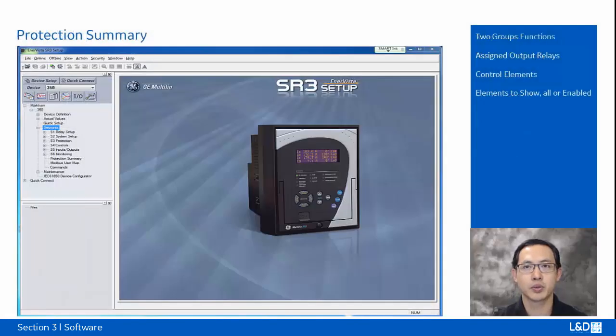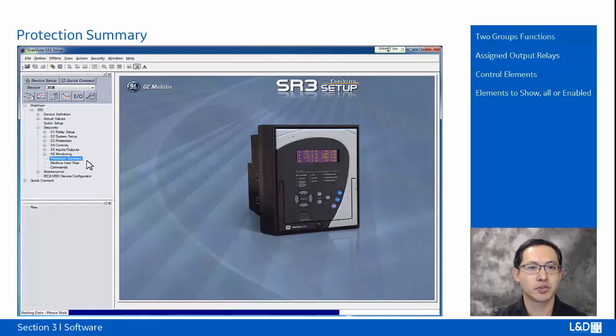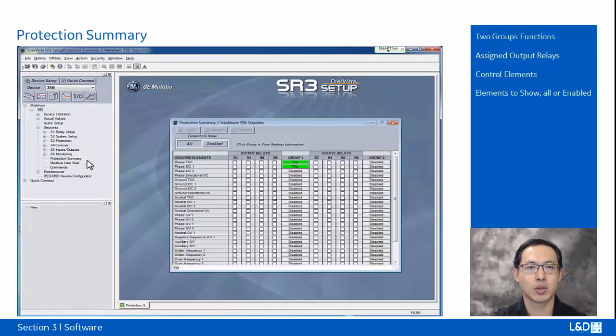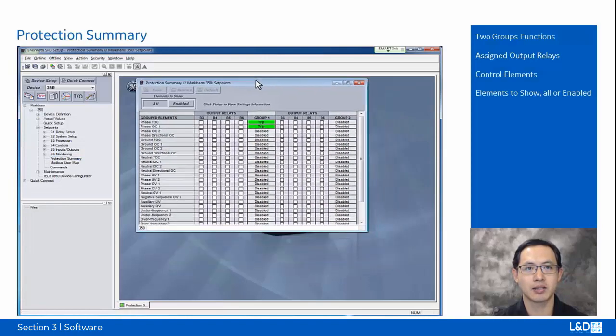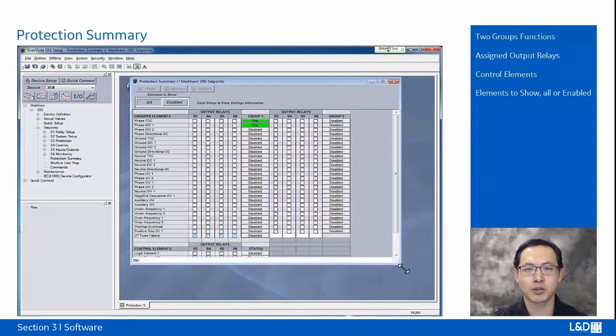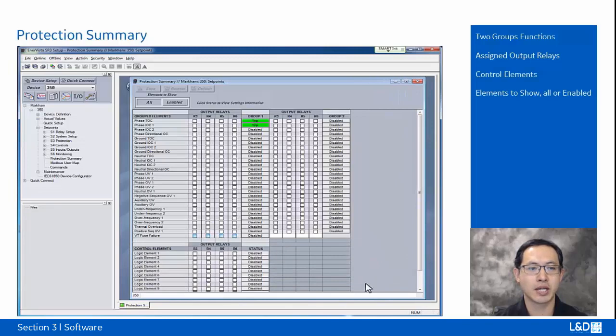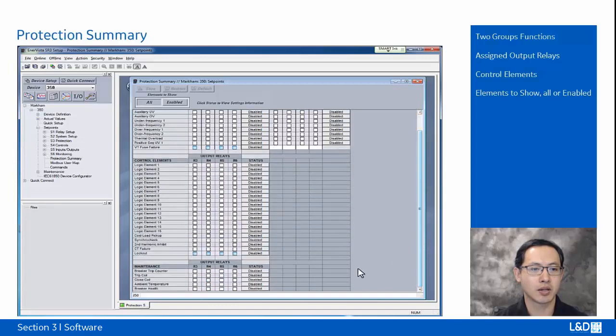Another way to do the quick setup is going through the protection summary. Under the protection summary, we can check which elements are enabled and which relays have been assigned for both group 1 and group 2, and we can also check the control elements like the logic elements and also the maintenance for each setup.